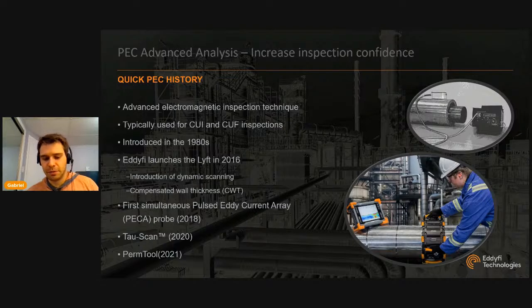So it's why the technique has been used since the 1980s as a screening tool for CUI, CUF. You can use PEC to find areas of interest and then strip only locally the insulation or the fireproofing to confirm the calls. So it's a very nice screening tool that saves a lot of cost in surface preparation and insulation removal. So instead of inspecting, say, 100 yards of piping and stripping the insulation, you can scan through the insulation, find a single area where you've got damage and strip only locally the insulation. So a lot of benefits to PEC.